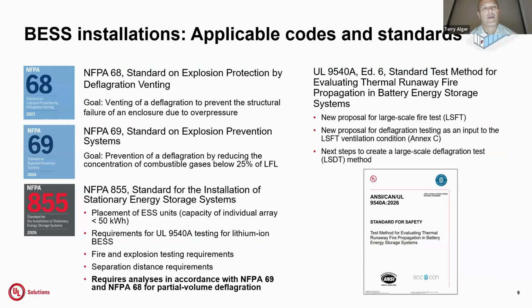So while we're talking about standards, we'll take a quick second to review the applicable codes and standards for BESS installations. When it comes to battery energy storage systems in the United States, the controlling codes are NFPA 68 and 69, which deal with explosion protection and explosion prevention. The only thing worse sometimes than a battery that vents and catches fire is a battery that doesn't catch fire right away, because unless you've got an acceptable explosion prevention system or a good explosion protection system installed in your BESS, you can have a pretty significant event if those vent gases build up before they ignite. Then overall we've got NFPA 855, the standard for installation of stationary energy storage systems. It deals with the placement and siting of ESS units.